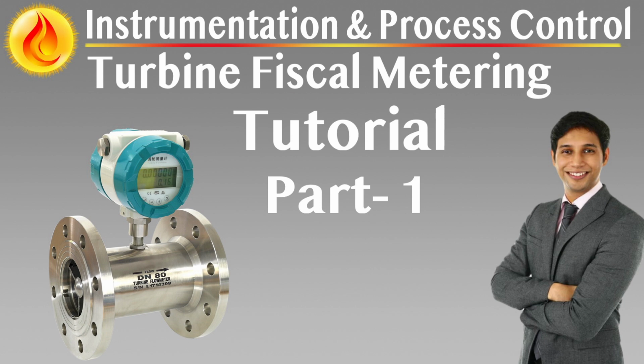Calibration equipment and tolerance hierarchy. Calibration tools, when part of the supplied system, must carry valid certificates from national laboratories or accredited agencies. The equipment must have a measurement uncertainty no greater than 1/3 of the instruments being tested.